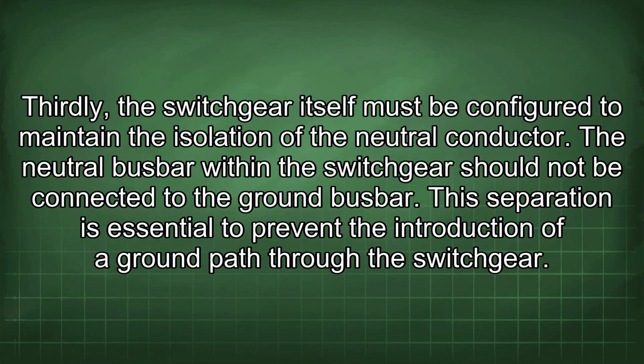Thirdly, the switchgear itself must be configured to maintain the isolation of the neutral conductor. The neutral busbar within the switchgear should not be connected to the ground busbar. This separation is essential to prevent the introduction of a ground path through the switchgear.